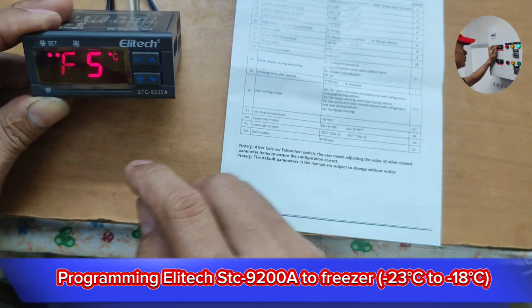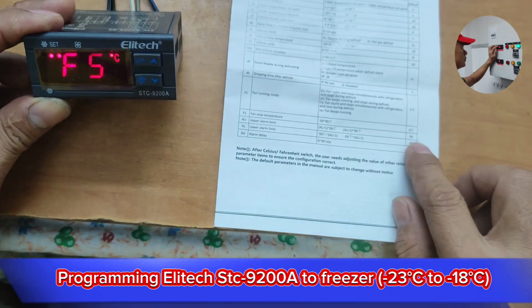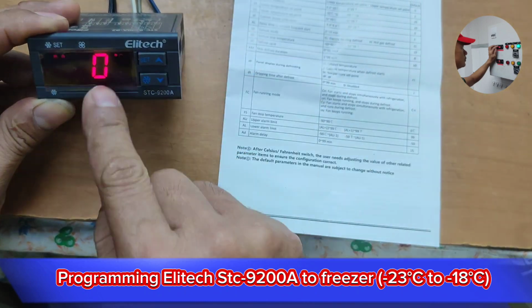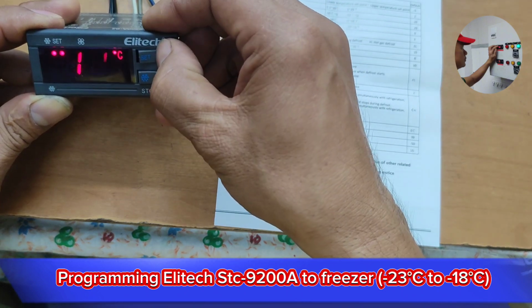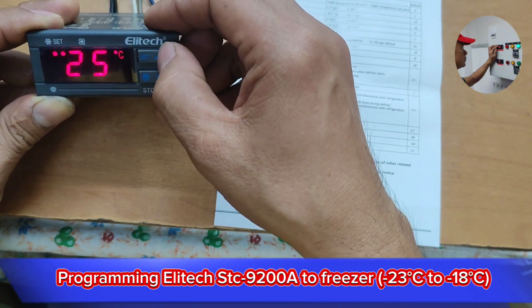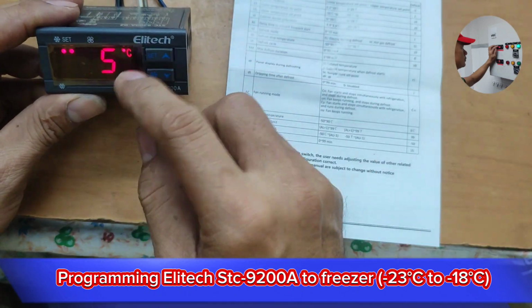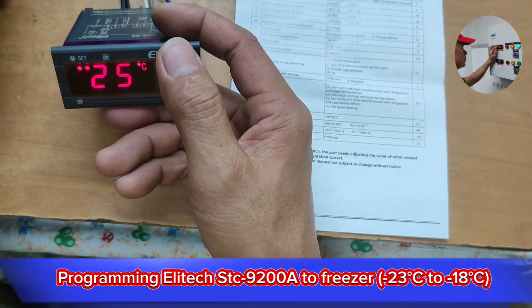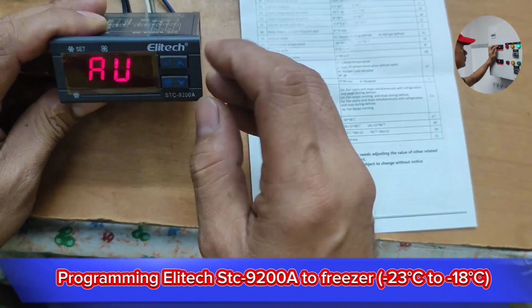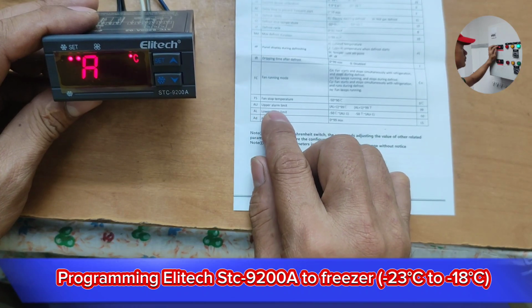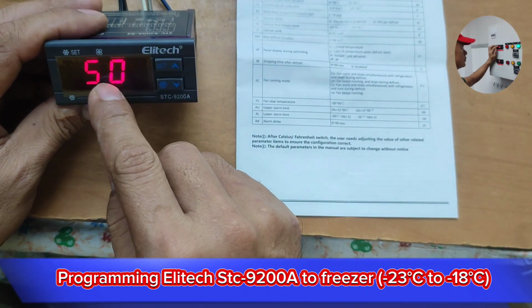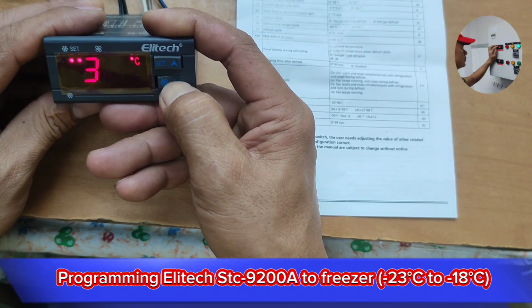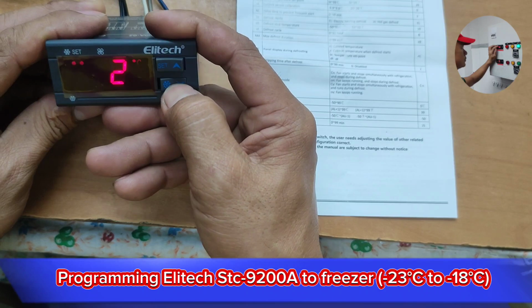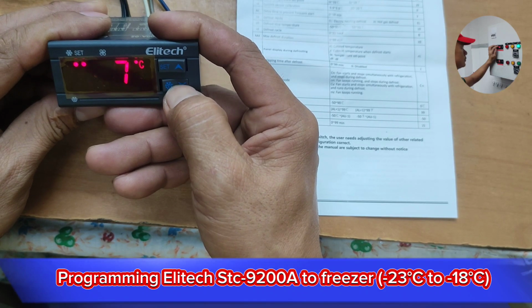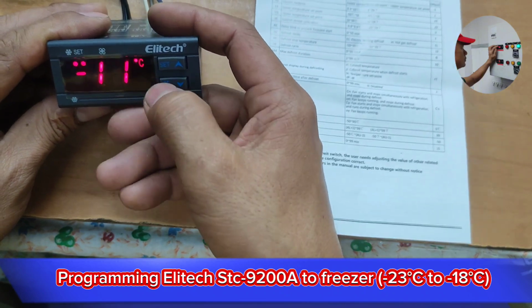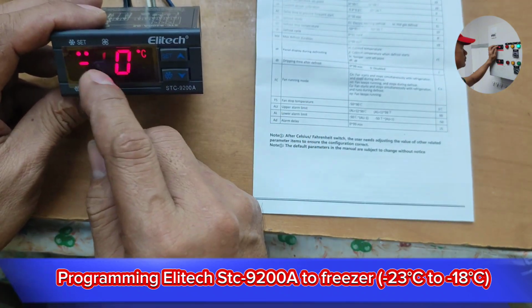Then press set. For the FS, fan stop temperature, the manufacturer set it to 0. We're going to program this to 25 ideally. So during startup, the temperature of the cabinet is 38 or something. When it reaches 25 degrees Celsius, the evaporator sensor senses that and it will activate the fan motor. Press set to memorize. And after that, AU appears, the alarm limit. Reset, and we're going to set this to negative 12. Negative 10, okay, no problem with that. So this will be my highest temperature.